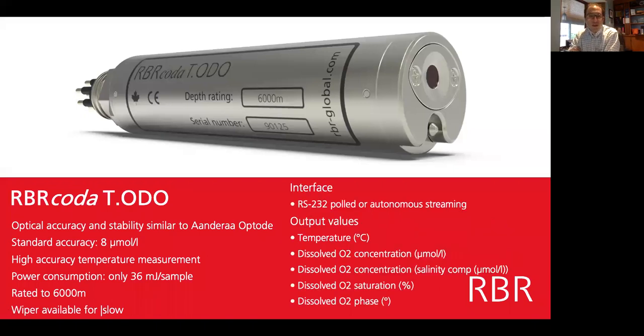In terms of the interface, it's a serial interface using RS-232 protocol that can be polled or it can stream the data continuously. And the output parameters that we provide are temperature in Celsius, dissolved oxygen concentration, also another parameter of concentration that's salinity compensated. If you have the CTD, we're pulling salinity from the CTD. If you don't have a CTD, you can input a fixed salinity. We're measuring, of course, and providing saturation and oxygen phase.